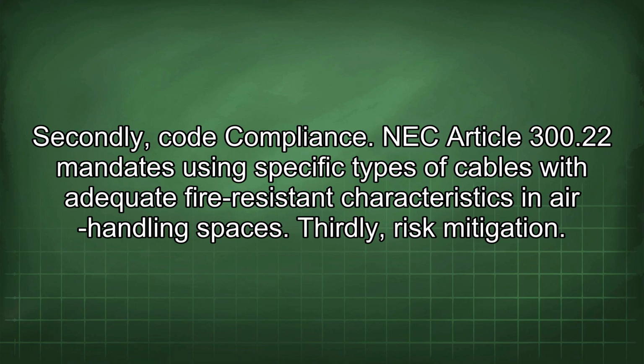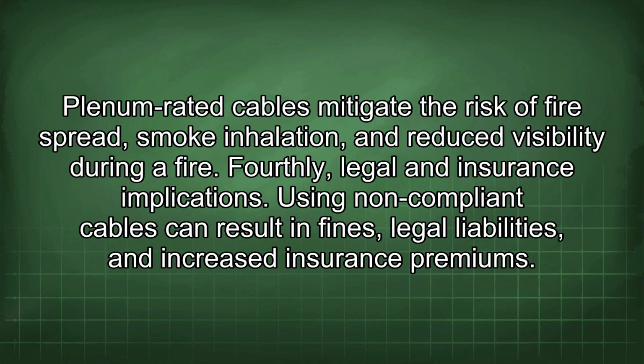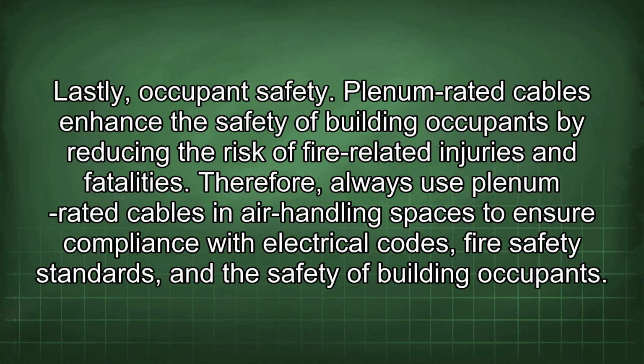NEC Article 300.22 mandates using specific types of cables with adequate fire-resistant characteristics in air handling spaces. Thirdly, risk mitigation. Plenum-rated cables mitigate the risk of fire spread, smoke inhalation, and reduced visibility during a fire. Fourthly, legal and insurance implications. Using non-compliant cables can result in fines, legal liabilities, and increased insurance premiums. Lastly, occupant safety. Plenum-rated cables enhance the safety of building occupants by reducing the risk of fire-related injuries and fatalities.